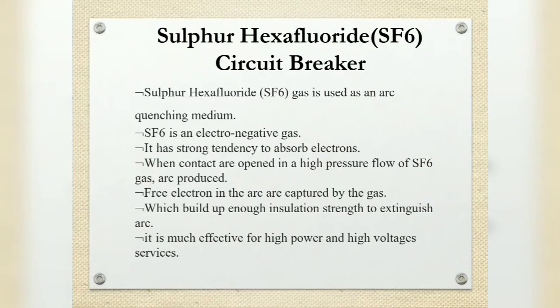SF6 gas is extremely stable and inert and its density is 5 times that of air. It has high thermal conductivity, better than that of air, and assists in better cooling of current carrying parts.